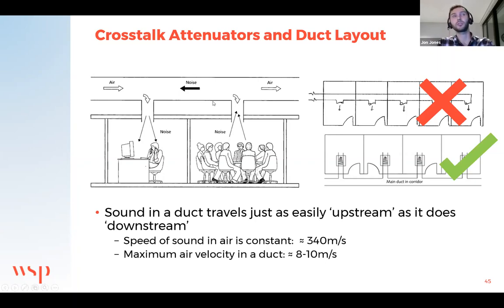Now, crosstalk attenuation or attenuators, you may or may not be aware, are essentially introduced where you have two rooms which are served by a common system, as shown in this section. What you can have is, say, a meeting room with a number of people talking, a common ductwork to another area, and you get a lack of privacy as a result of this sort of arrangement. So introducing a crosstalk attenuator in the middle just means that any noise that does break into the duct is attenuated and shut down there.